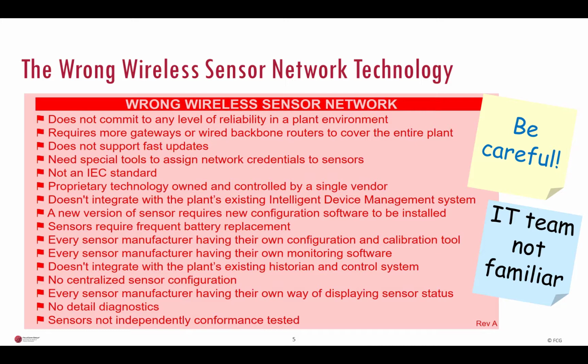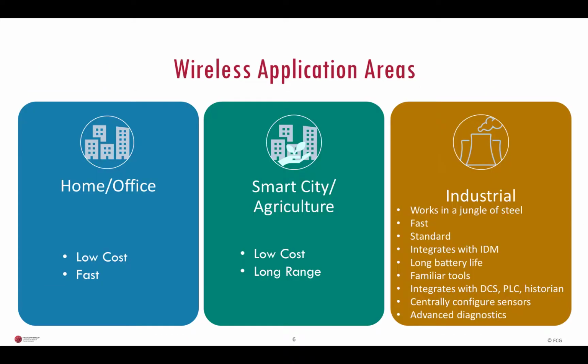The site IT team is not familiar with a plant full of steel or replacing batteries in sensors or Modbus or OPC, DCS, historian, or device management software, and not familiar with sensor configuration or vibration spectrums. So the I&C team must therefore take the lead to guide in the sensor network selection. Now, one size does not fit all. Therefore, there are many wireless technologies with different characteristics to meet the different needs of various application areas.